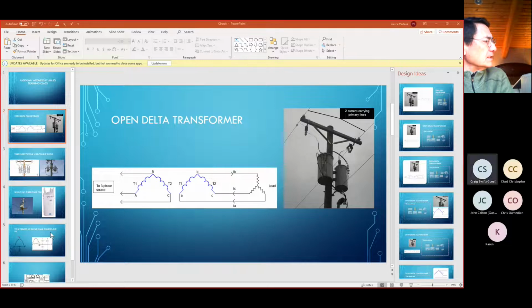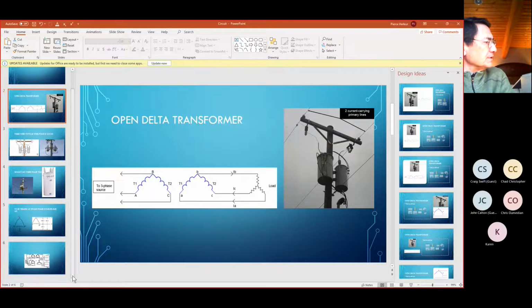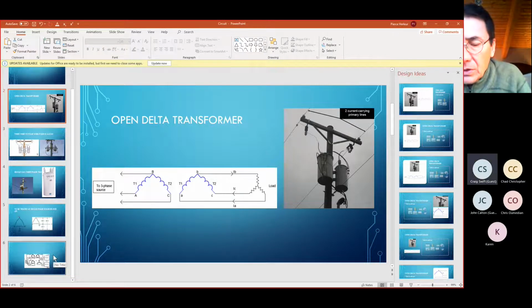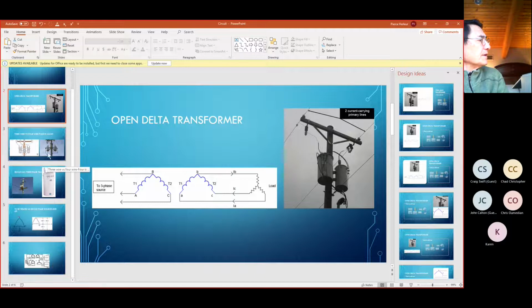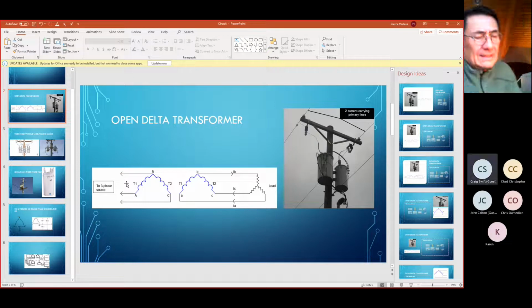I'm surprised at that, frankly. I find that a little bit disturbing because the open delta transformer requires upsizing of the drive. The voltage variances on it are significant, and okay, well, let's deal with this.